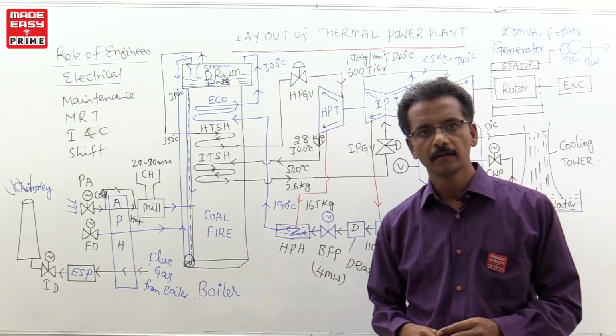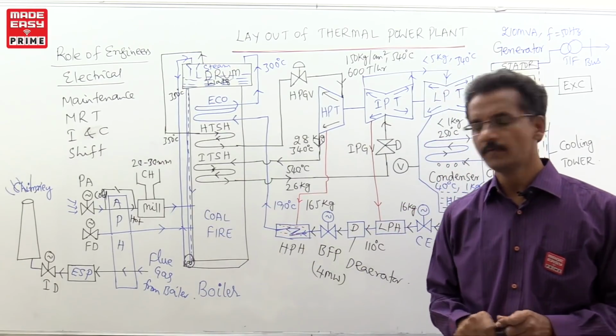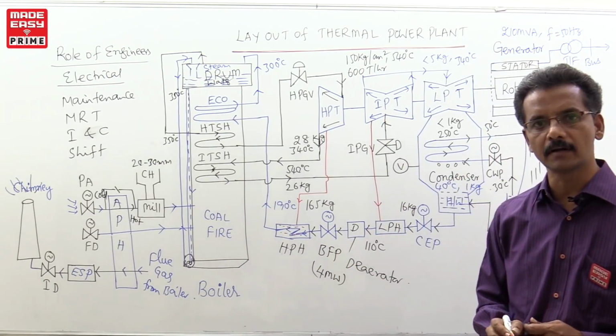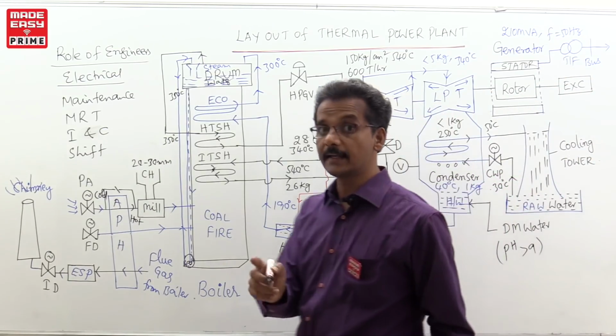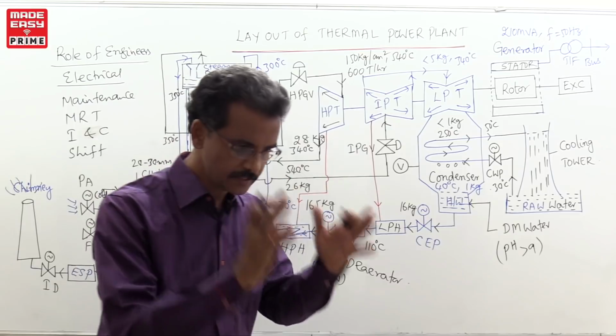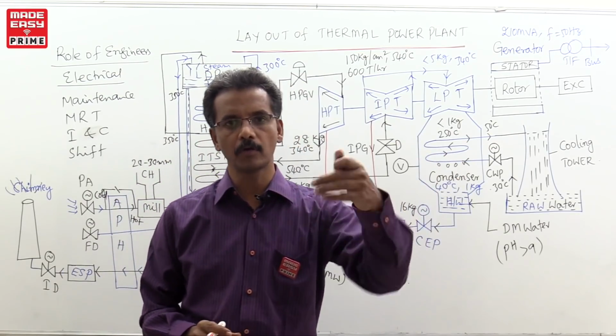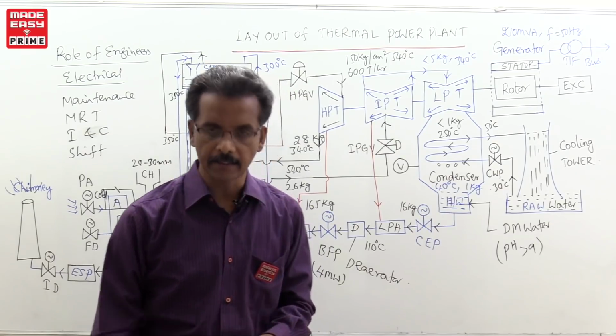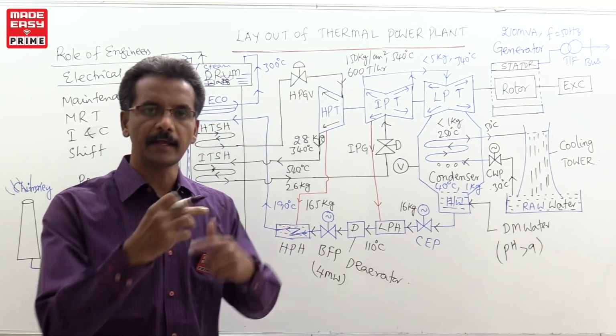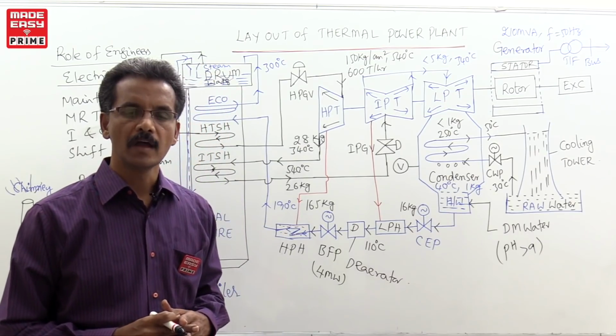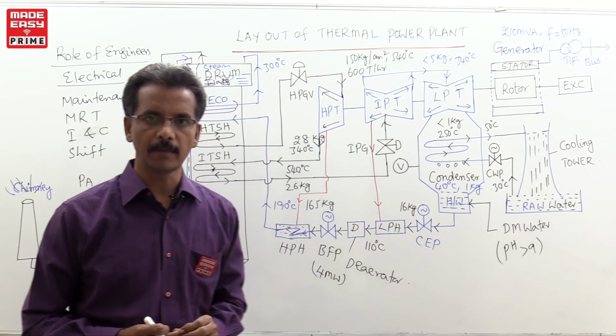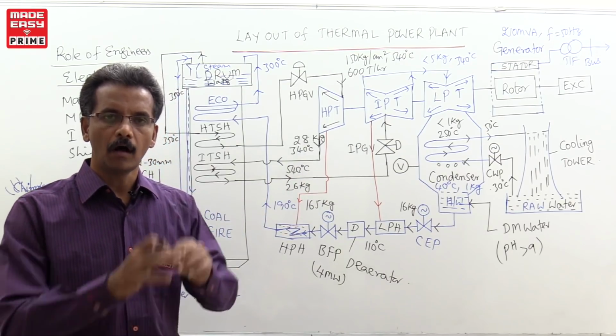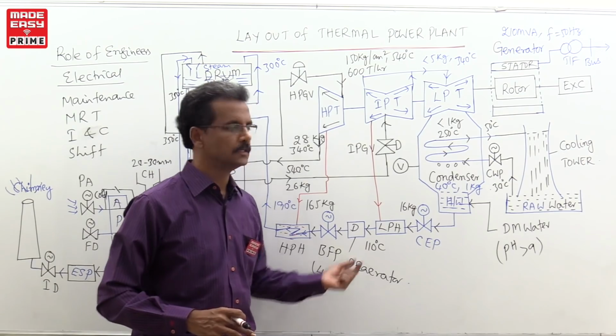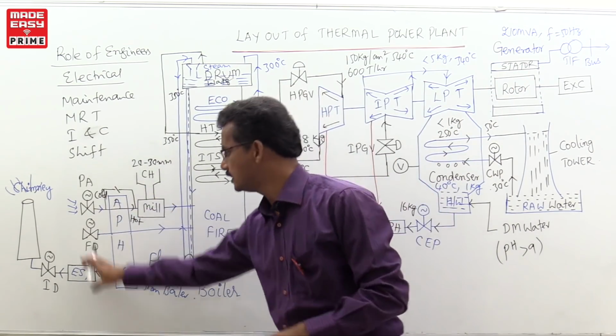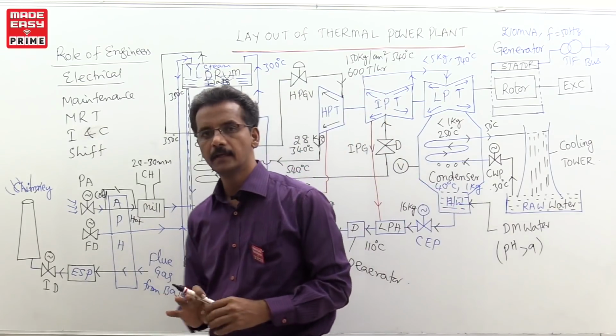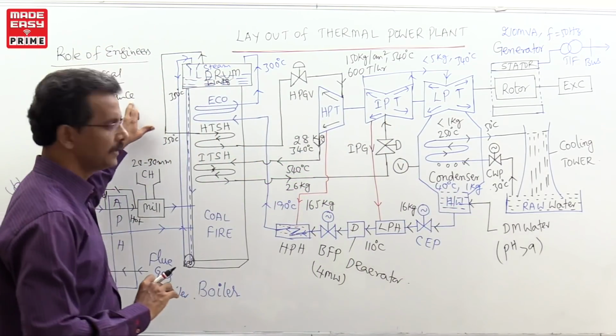How will the pumps work? For that we are using different sizes of motors. For example, this BFP, as already told, is 4 megawatts of power. For a 4 megawatt electrical motor running, whether this motor is running properly or not, whether it is taking a proper input voltage, whether the output current is within the rating, whether the internal cooling mechanism of the motor is proper or not, and whether any abnormal noise is coming or any heating is there inside the motor. All these observations of each equipment, motors, generators, transformers and these fans, fan motors, will be taken care of or looked after by the maintenance people.